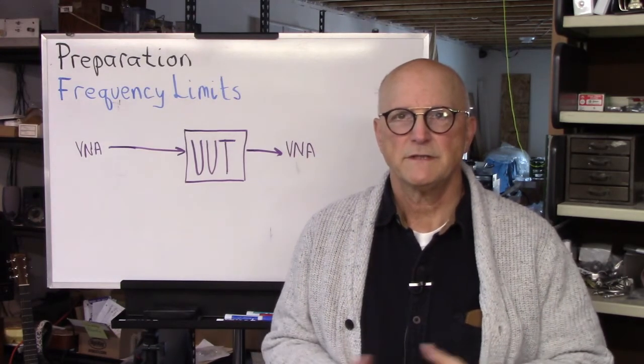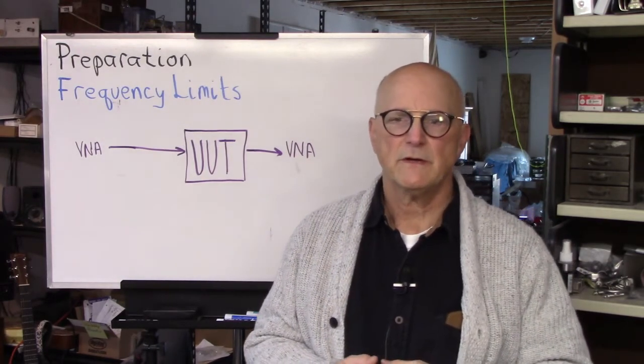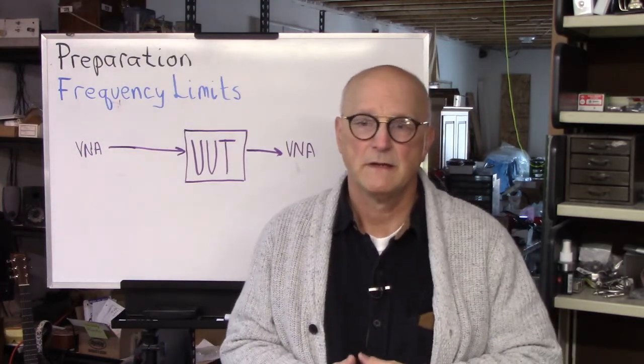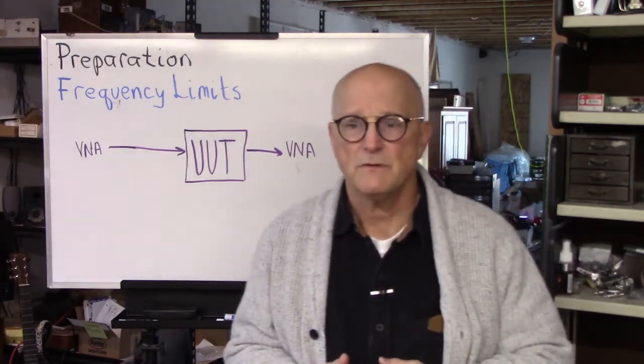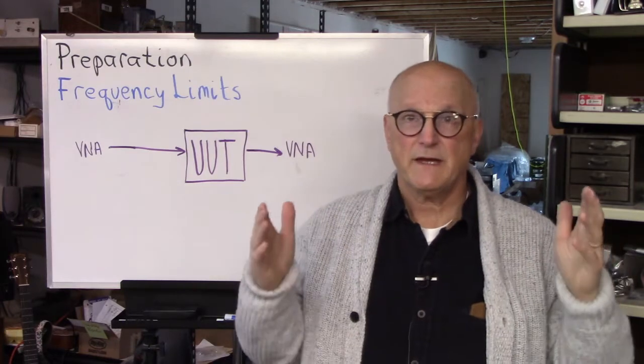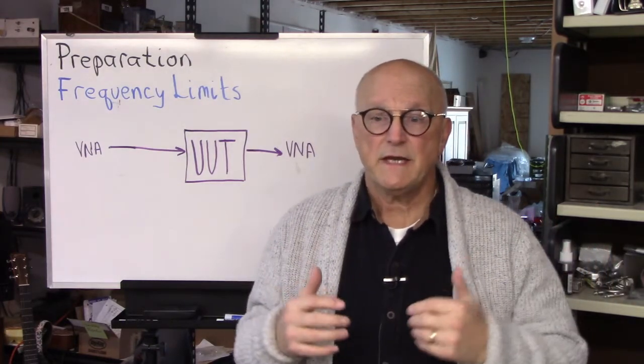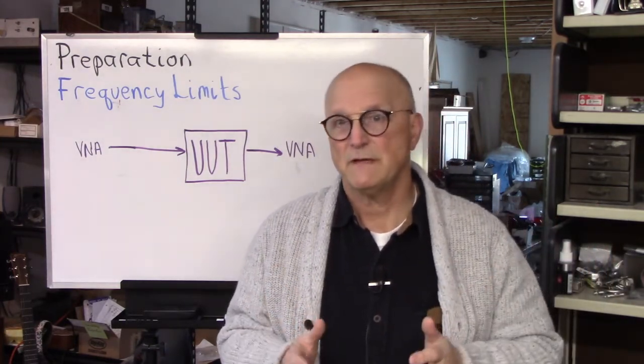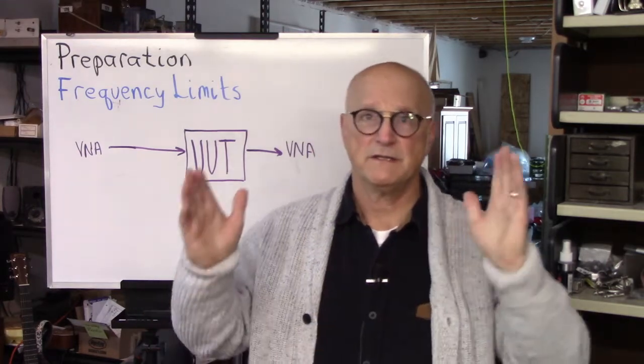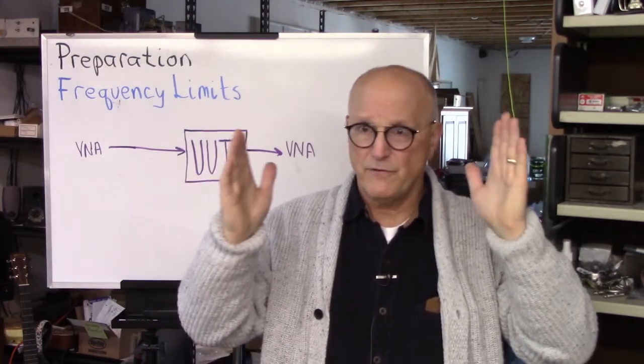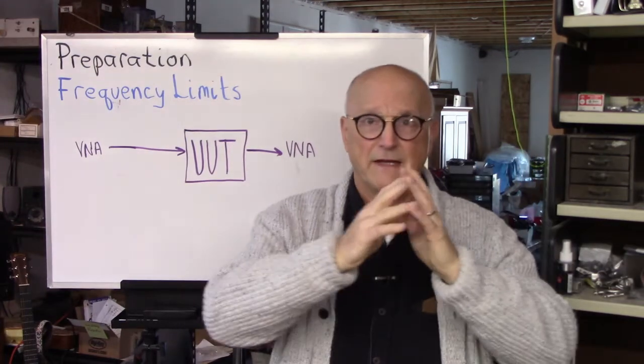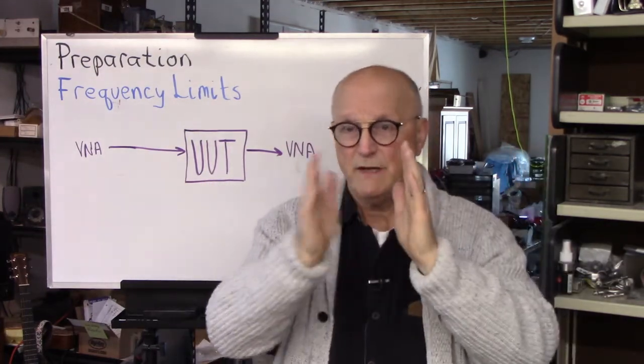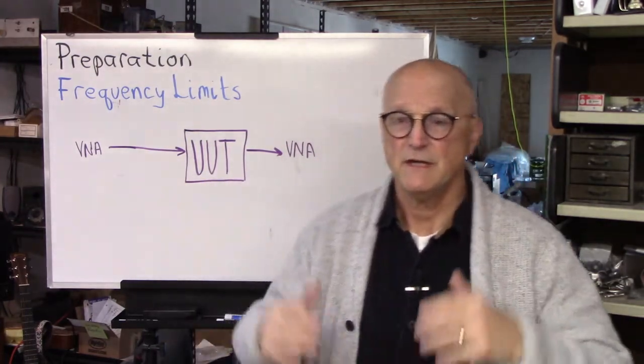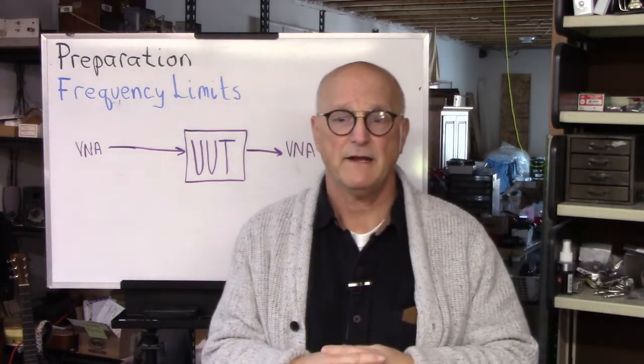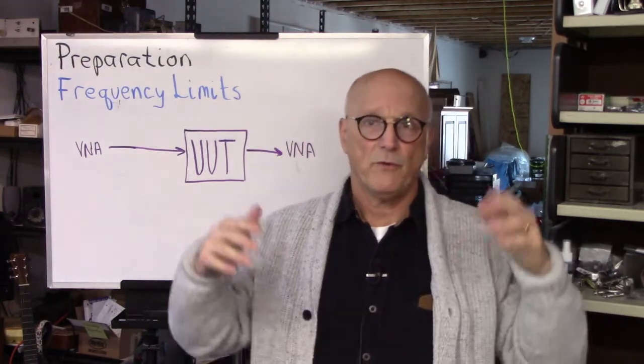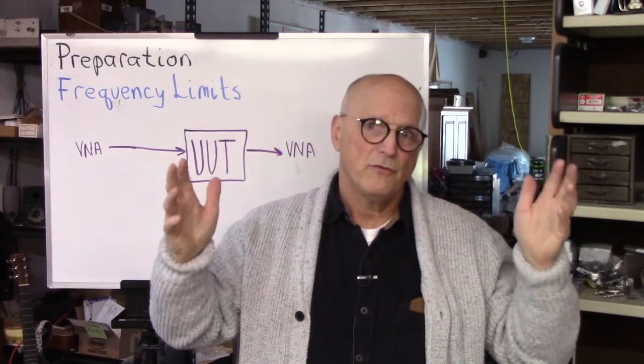Next, we have to consider the frequency limits that you're calibrating and measuring to. Now, some VNAs will let you set the frequency limits of the calibration. In this case, it's important to set the frequency limits before you calibrate, because the narrower your frequency limits are, the less interpolation there is between each of the samples it takes to set up that calibration.